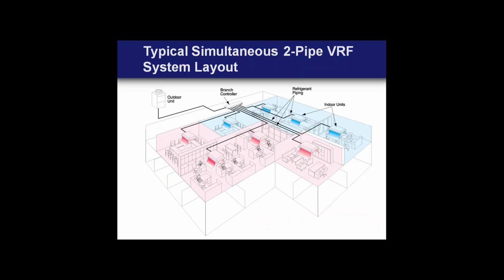Again, looking at the piping layout, in the case of Mitsubishi's heat recovery system, you'll have a high and a low pressure pipe from that outdoor unit to the branch controller. Inside of that branch controller are several devices. One of the most important ones is a gas liquid separator. That's what allows the separation of states when you're in a cooling dominant heat recovery mode.